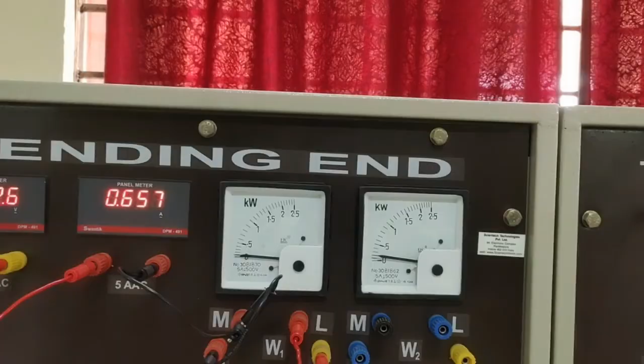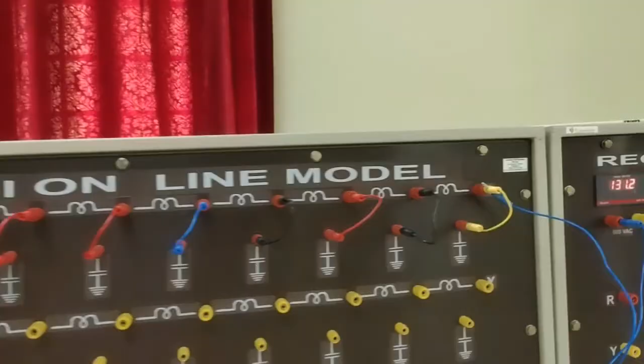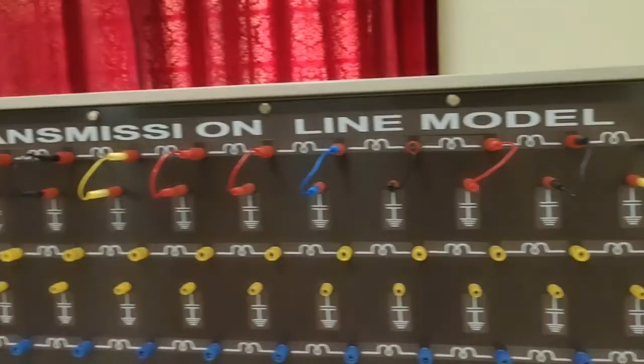The receiving end is open circuited, so you can calculate the open circuit voltage. You apply the rated voltage of 230 volts at the voltmeter, and you can see the voltmeter readings accordingly on the variac, along with the wattmeter and ammeter readings for the open circuit voltage and current. So this is 230 volts.